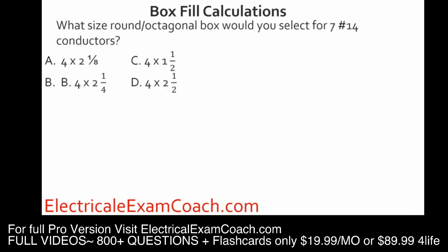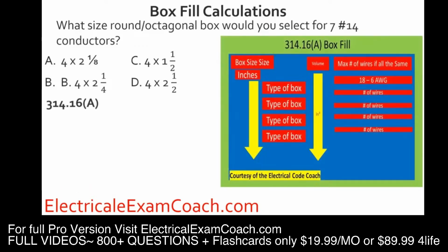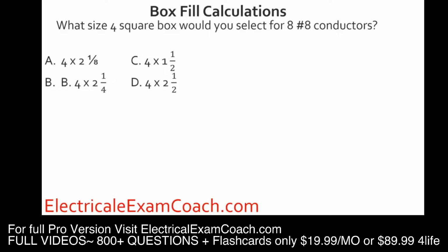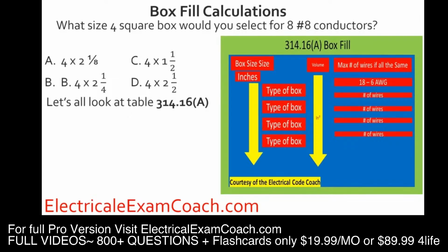What size round octagonal box would you select for 7 14 gauge conductors? We're going to head to table 314.16a. We're going to start here on the right-hand side and we're going to find our gauge wire. Then we're going to come down and find a box that fits it and be sure when we cross over that we stay in the right category of box, and we're going to select C. What size 4 square box would you select for 8 number 8 conductors? We head to 314.16a. We're going to start here on the right-hand side and we're going to find our size wire. Then we come down and make sure that we're in the right type of box. We cross over and we're going to find that it's A.